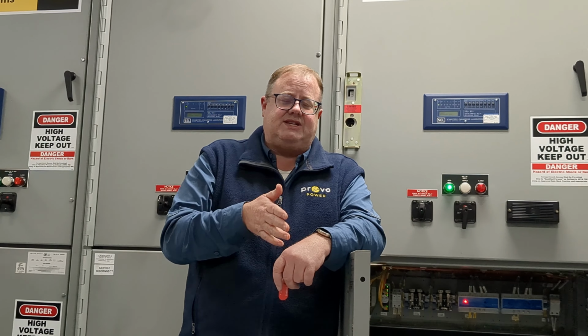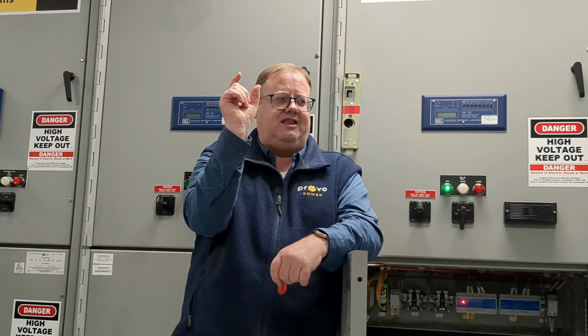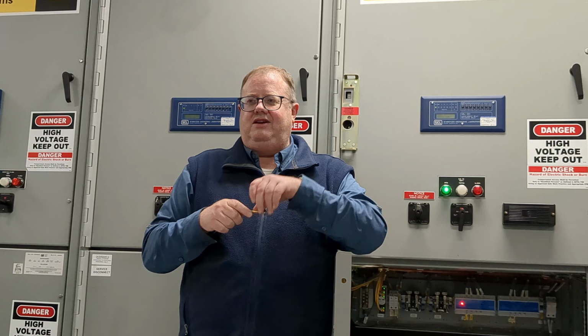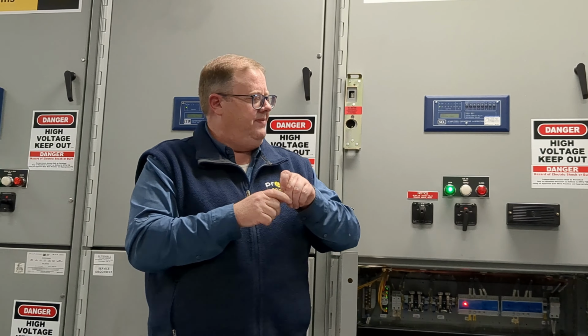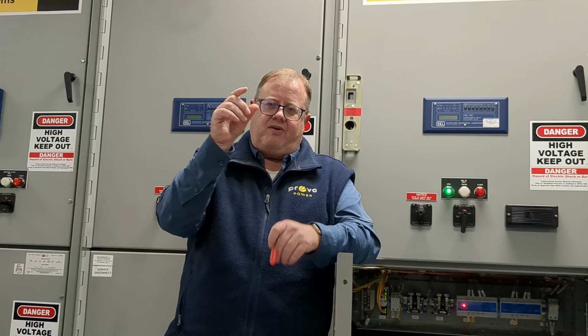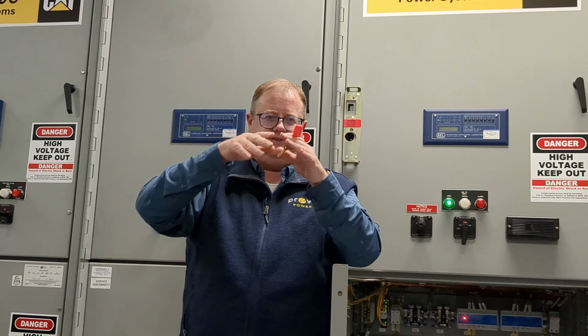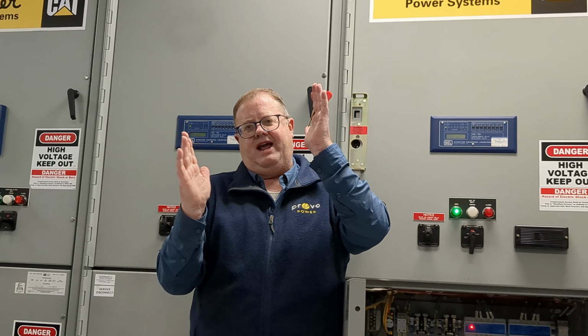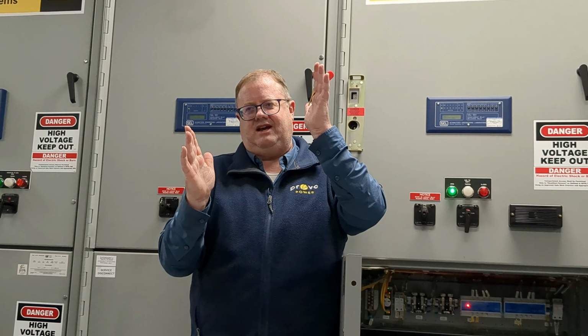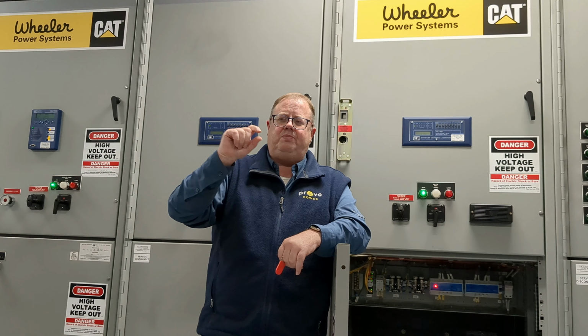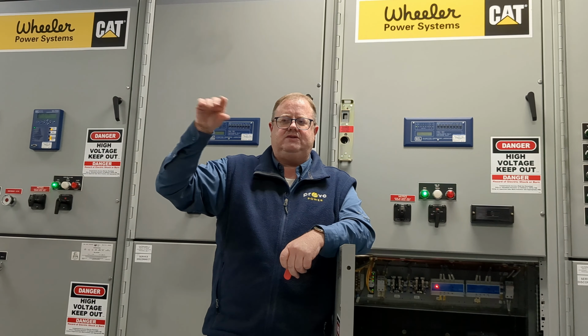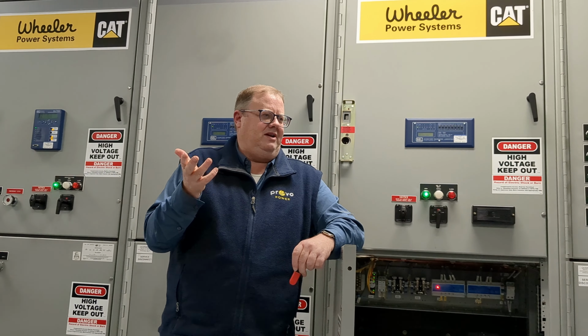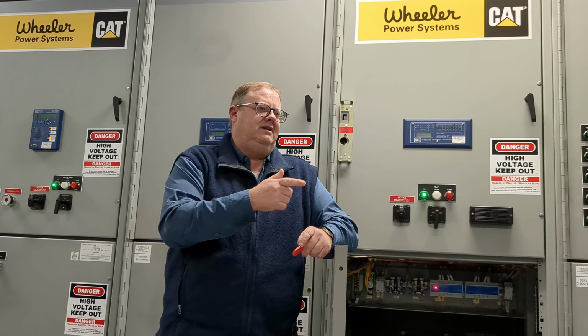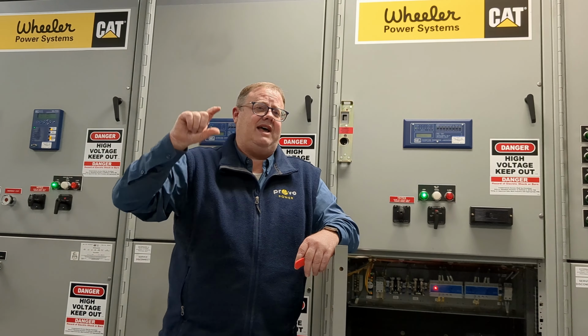If it closes and the fault's still there, what we're hoping is that the fuse will blow. So what you do as an engineer, you look at the fuse coordination, you program the relay to operate with the fuse. You look at these curves and you try to operate it from, you know the current, you know how much fault current is on the system, and you try to operate the fuse right after the first breaker. And then if the fuse blows and then this closes, then most people are on. The only people who are affected are the small amount that are affected by that fuse. So as an engineer, that's kind of what you do when you talk about fuse coordinations. You're coordinating the breaker with the fuse out in the system.